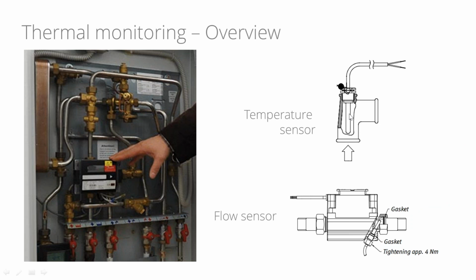So instead of just putting a probe or just installing a current transformer like in electricity, here what we have to do is introduce the sensor inside the pipe. Oh, wow. So maybe you have to change some piping. Right. Okay. So that's what I explained to the partners, that installing thermal sensors is not always very easy, because you have to take apart some stuff. Exactly. And maybe take some parts of the piping and install a different one. So installing, for instance, T piping or Y piping, right, to introduce the temperature sensor or the flow sensor itself.